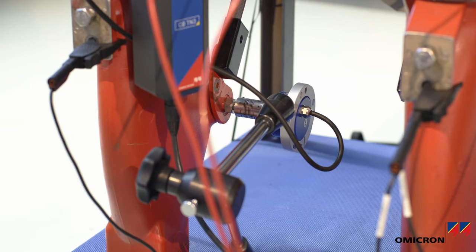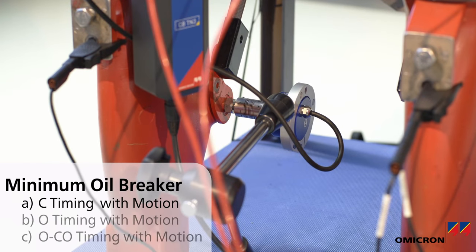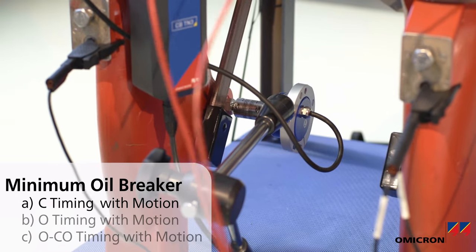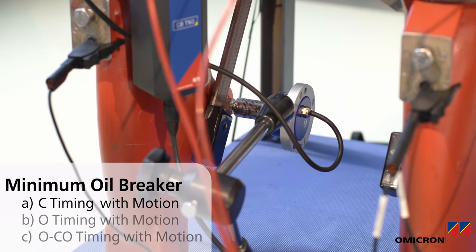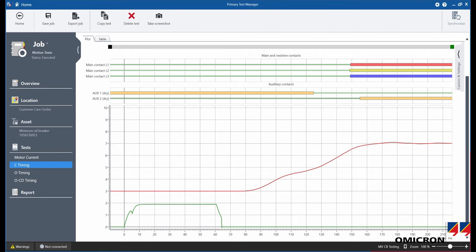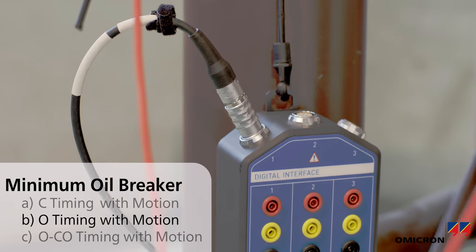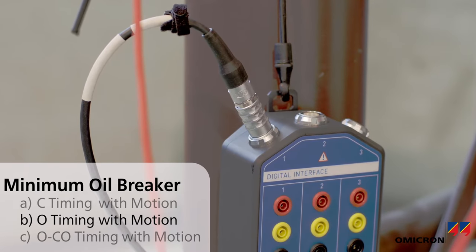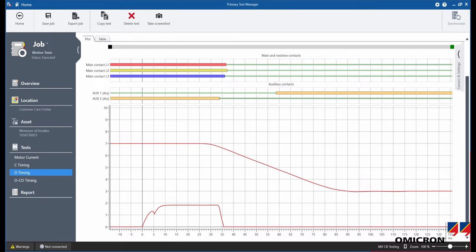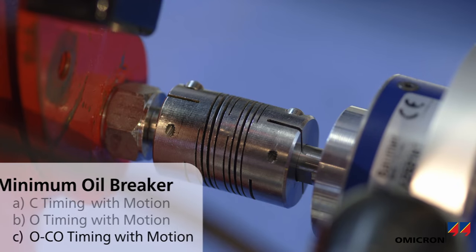Motion curves can also be recorded during the timing tests using digital motion transducers and the CB-TN3 connection modules. Motion tests show the mechanical movement of the operating mechanism during an operation and can be performed on all timing tests. The combination of time and motion measurements provides important additional information about the condition of the circuit breaker's moving parts.